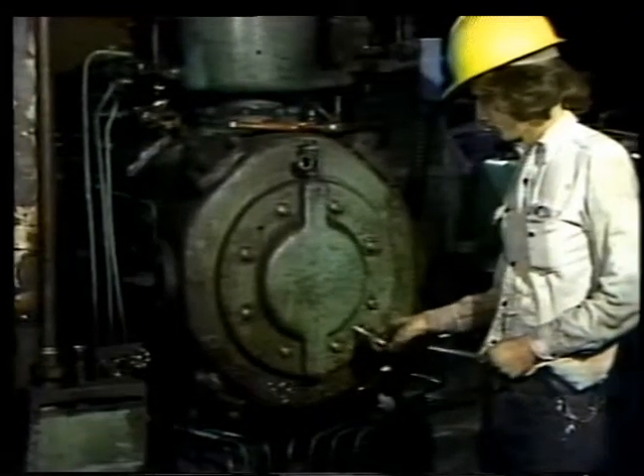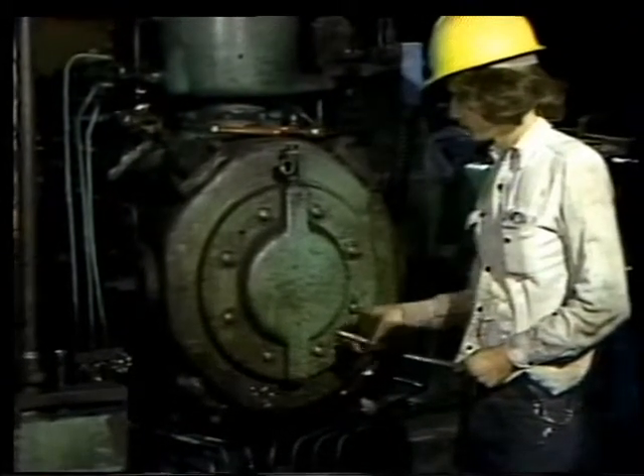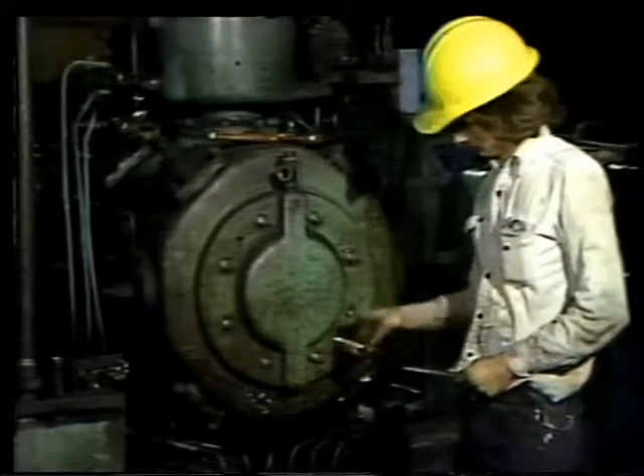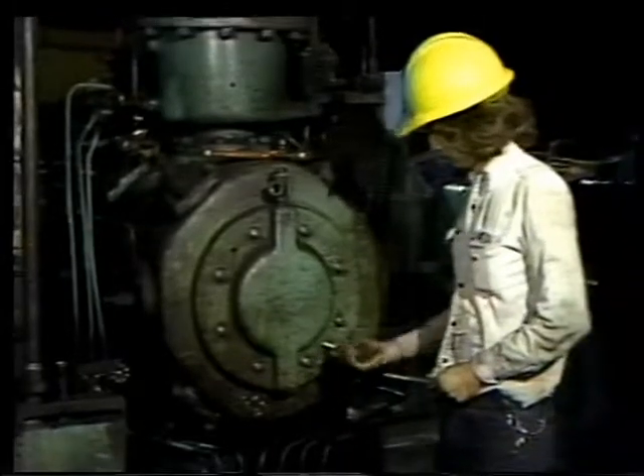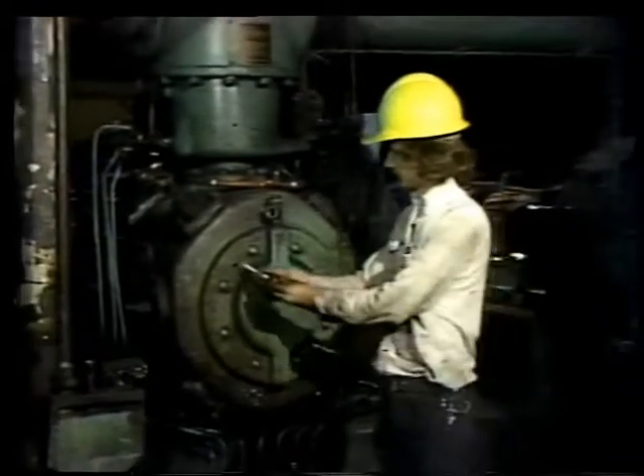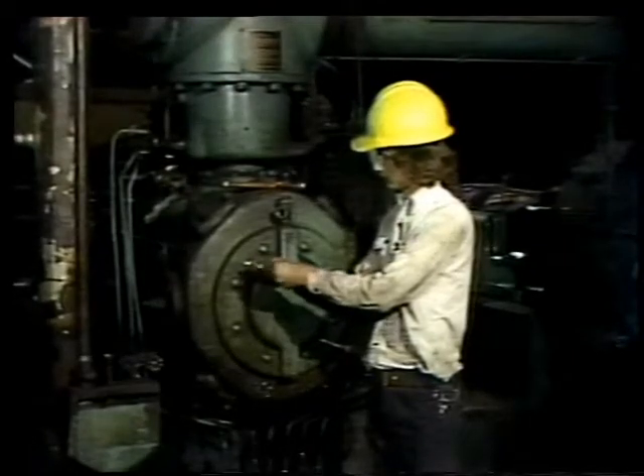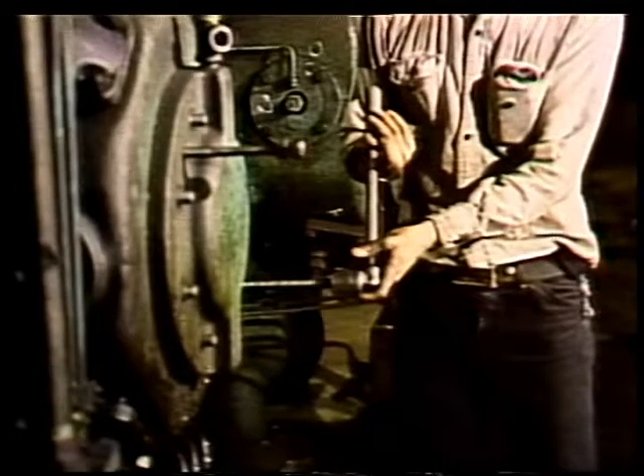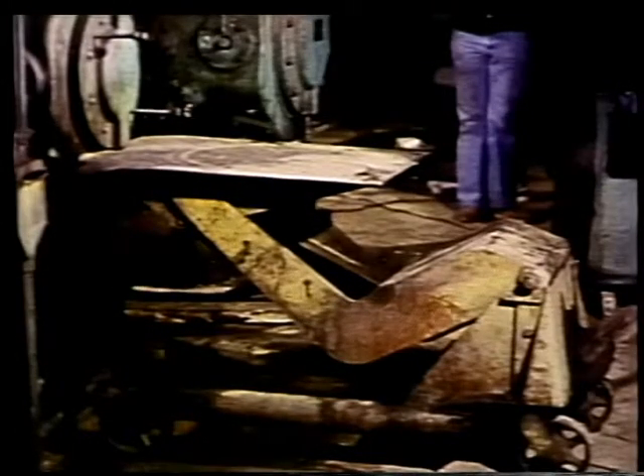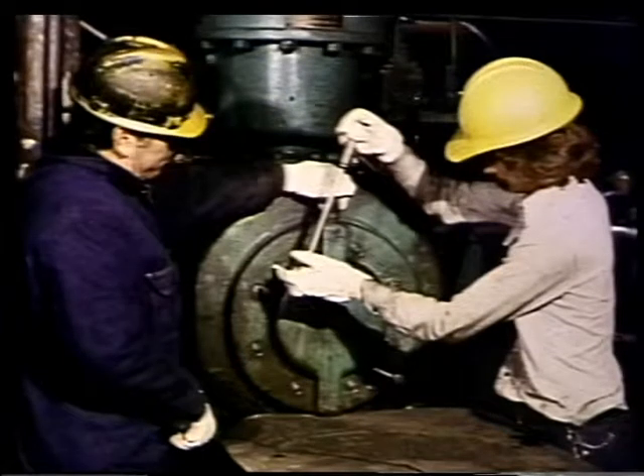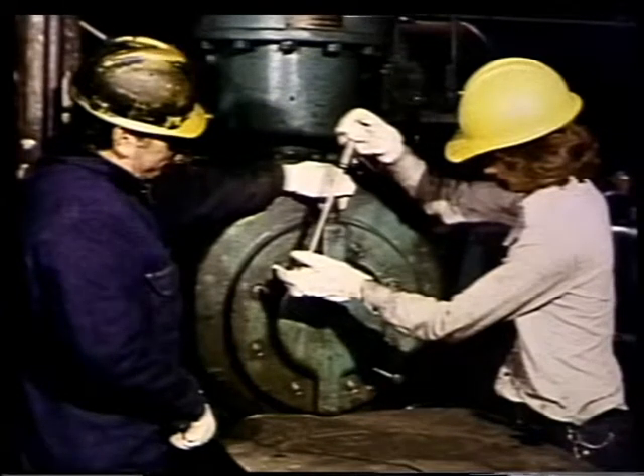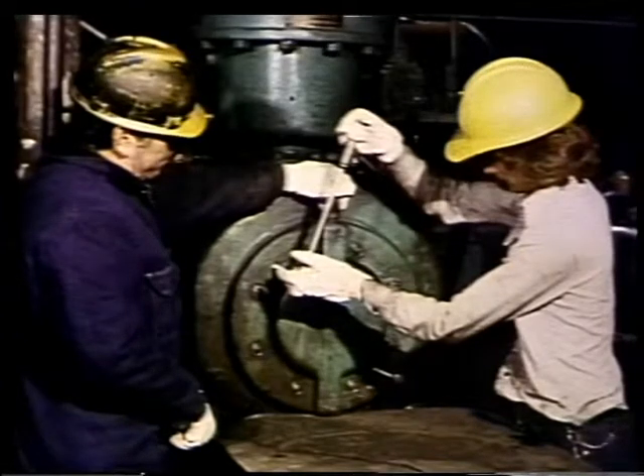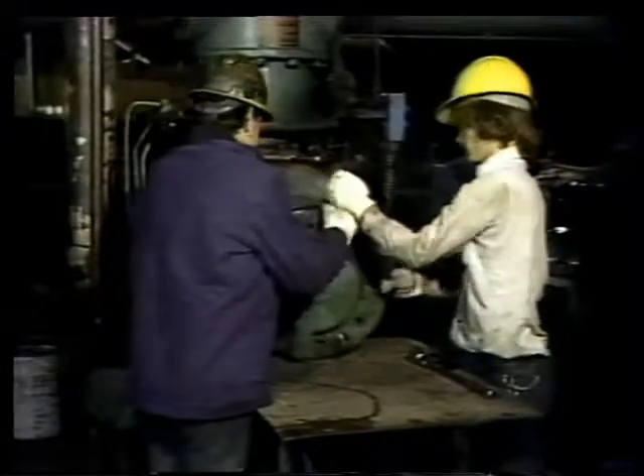First, tighten the bolts by hand. Then, use a wrench to tighten them. Tighten them alternately to ensure that the head is forced evenly away from the cylinder. Here, a portable table is used to support the head. Once the table's in position, the jacking bolts are turned to force the head completely off the studs. Then, with the help of another mechanic, you can pull the head off.